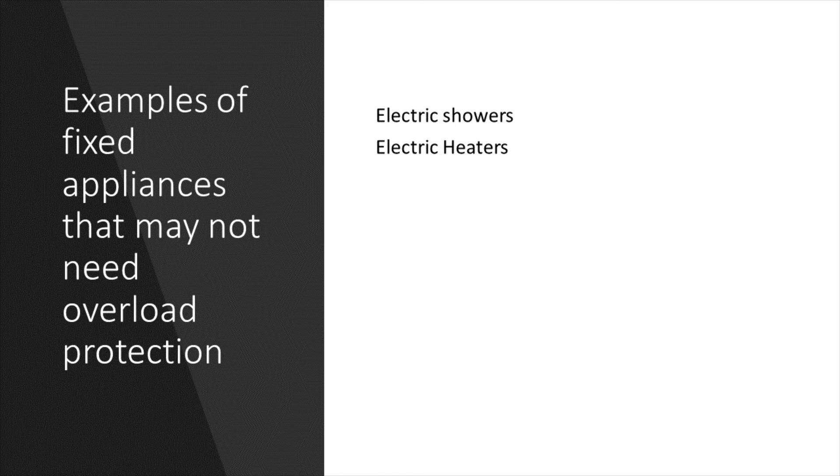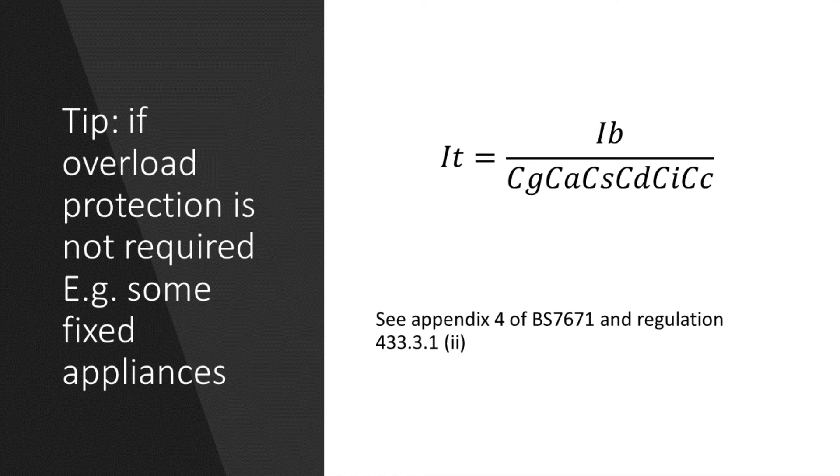Now when we say that overload protection need not be provided, in reality the overload protection device, such as an MCB, is installed. But what we can do is, when we calculate the IZ of the cable, we can divide the design current by the correction factors rather than the rating of the protective device IN.